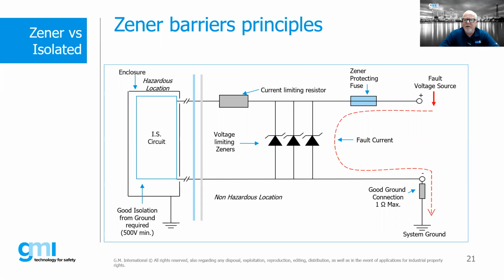Now if that energy starts going too high, ultimately it will blow the fuse. At that point, our barrier has been taken offline - we are not going to get a signal out to our field device, and we would need to replace the barrier.